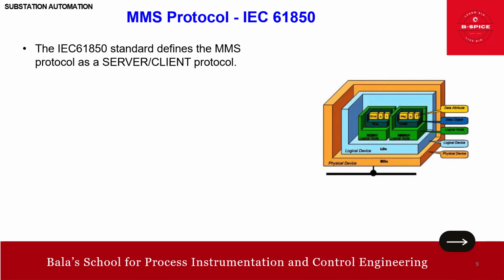MMS operates on a client-server model, facilitating communication between IEDs and higher-level entities like the remote terminal unit and SCADA system over Ethernet. It allows clients to access the server's data model, read or modify individual values, delete entries, and transfer files. This is essential for monitoring and controlling substation equipment - basically, it's used for data access.